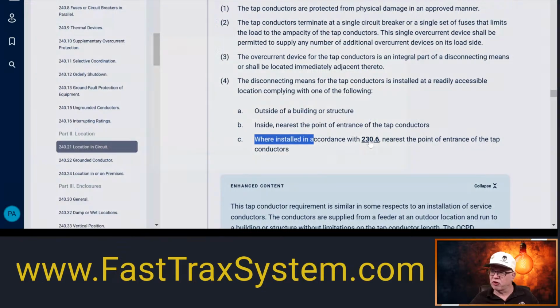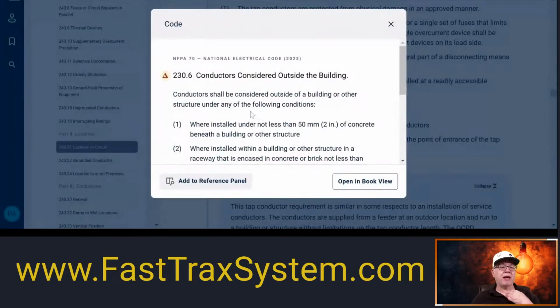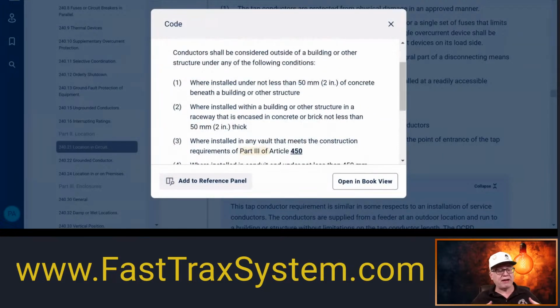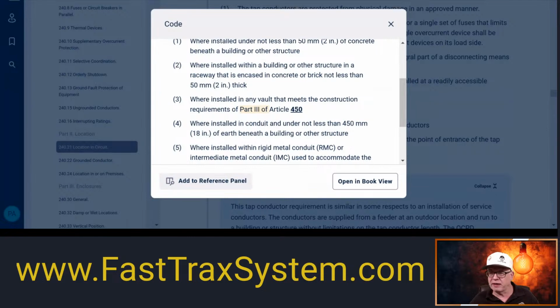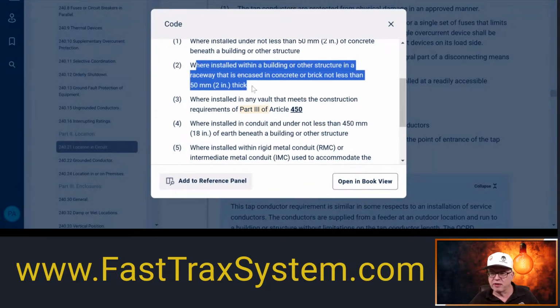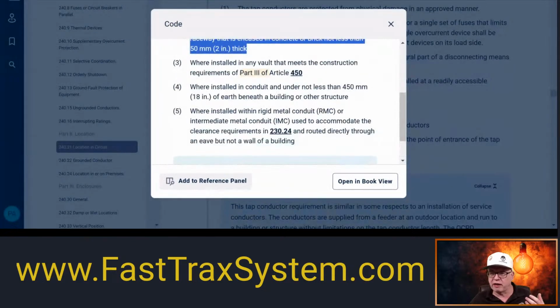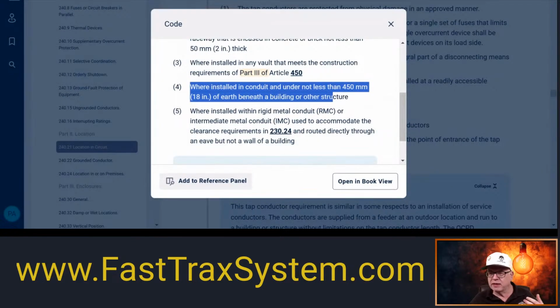And then it says installed in accordance with 230.6, the nearest point of entrance of the tap conductors. Now, 230.6 is when we're talking about conductors that are coming in from the outside in any of these applications, like in concrete. So you could have the conductors come into a building and then into a concrete column and continue on encased in concrete, 2 inches of concrete, okay? Here we're talking about the raceway encased in concrete, not less than 2 inches. There are other allowances here, like being underground 18 inches beneath the building and things like that.